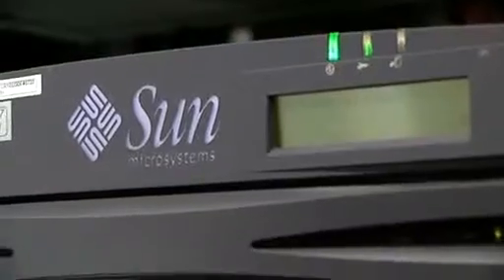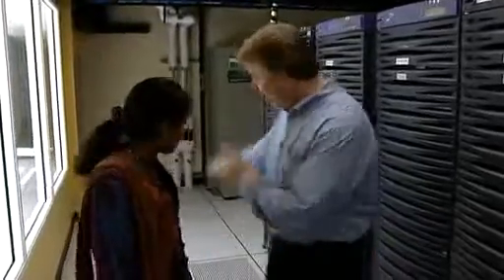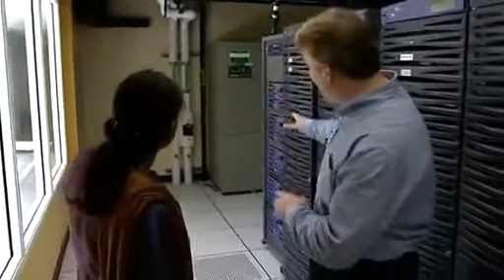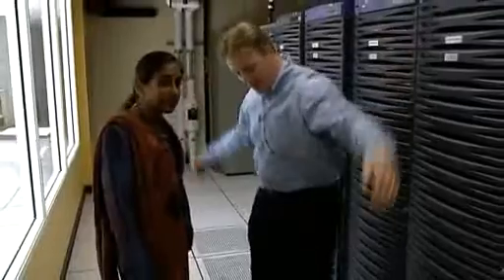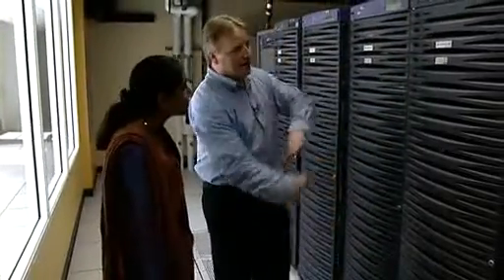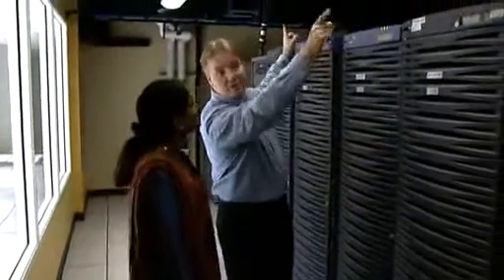Because one of the beauties of my job is all the next generation products that are going to our data centers for our customers in 2 to 3 years are in my data centers first. And so we really have to solve the density challenges beforehand. So if you notice, we're inside of a traditional data center with a raised floor and cooling units on the wall. And so they usually blow cold air down. It comes up through these aisles. And then it goes through the servers, comes out, and finds its way back to the actual cooling units. So that's the traditional way.